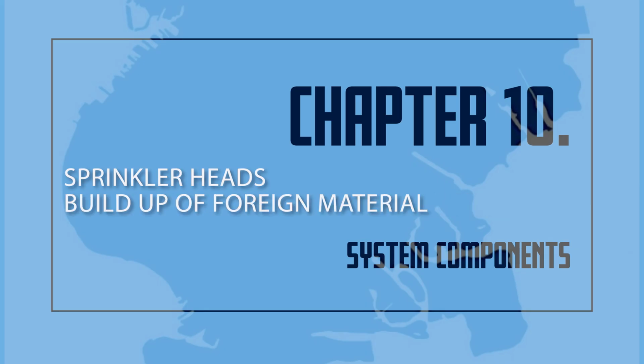Buildup of foreign material on sprinklers. Sometimes conditions exist which cause a buildup of foreign material on sprinkler heads. This may prevent the sprinkler head from working properly. This buildup is commonly called loading. The buildup of foreign material insulates the sprinkler head. This buildup prevents the sprinkler from opening at the desired temperature. If the buildup is hard, it may prevent the sprinkler from opening.